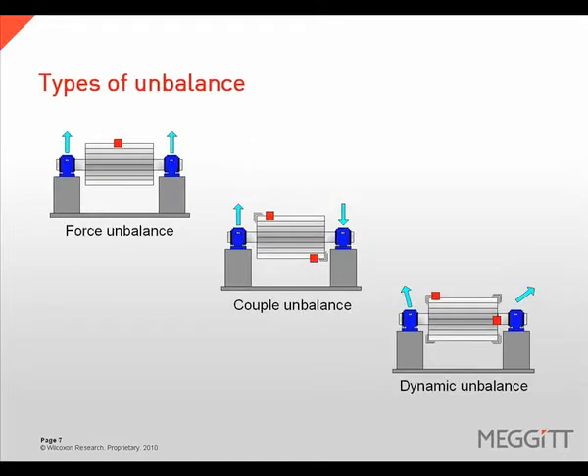There are three types of unbalance: force unbalance, couple unbalance, and dynamic unbalance. All three types exhibit vibration at 1 times rotational speed. To distinguish between them, we need to use phase readings. The phase is represented in the presentation by the turquoise arrows.